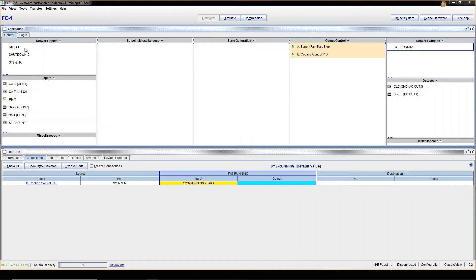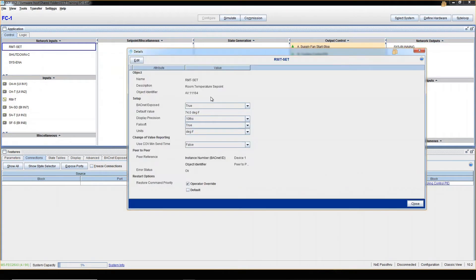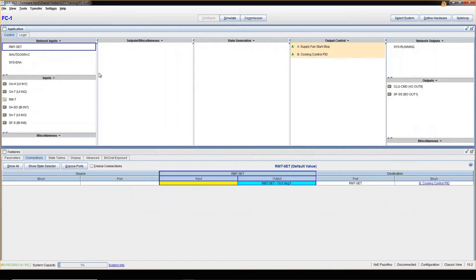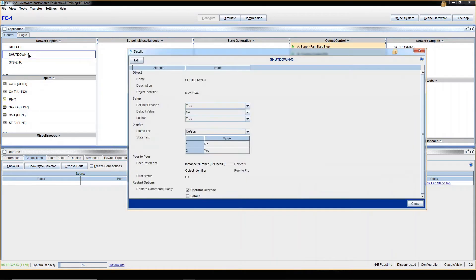For room temperature setpoint, if I double-click on it, the first thing I want to look at is the default value. You can tell that it's a number with units — degrees Fahrenheit. So since it's a number, it's a Float. Remember, floats are always numbers and digits. So that's a Float. Let's see shutdown command — I'll double-click on it.